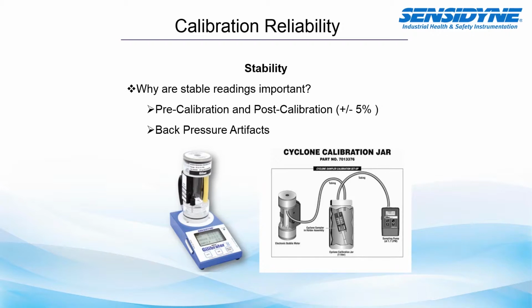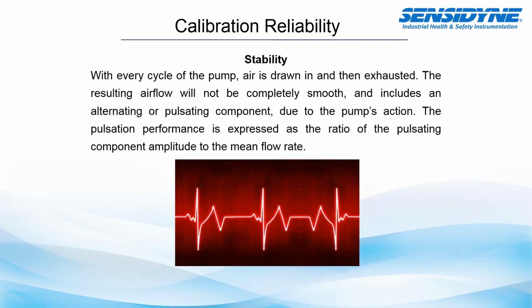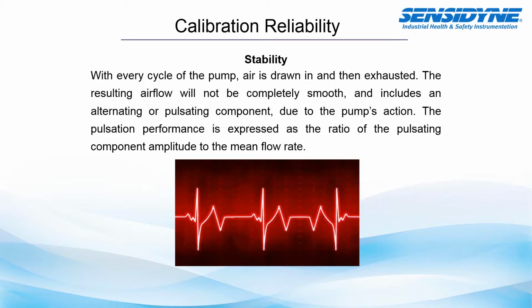Now, why are stable readings important? Again, to make sure that pre and post calibration remains within plus or minus 5% of your desired or initial set flow rate, and to ensure that back pressure artifacts from your calibrator are eliminated wherever possible. So think about every cycle of the air pump. Air is drawn in and then exhausted through the pump. The resulting airflow will not be completely smooth, and it includes an alternating or pulsating component. This is due to the pump's action with most common pumps out there, which use a pneumatic system to create the vacuum and positive pressure that your pump produces. The pulsation performance is expressed as the ratio of the pulsating component amplitude to the mean flow rate.